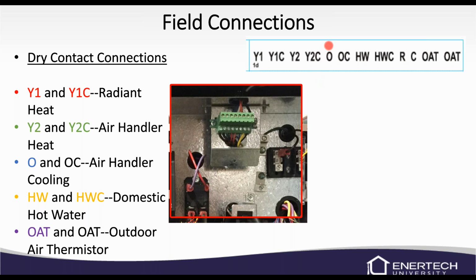If you jumper O to OC, that's going to give you an air handler cooling call. You jumper HW to HWC, that's your domestic hot water call. R, we're not going to worry about. C, we're not going to worry about. And OAT and OAT, that's where you're going to mount your factory supplied outdoor air temperature sensor.